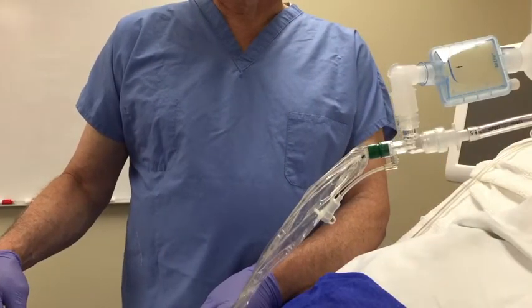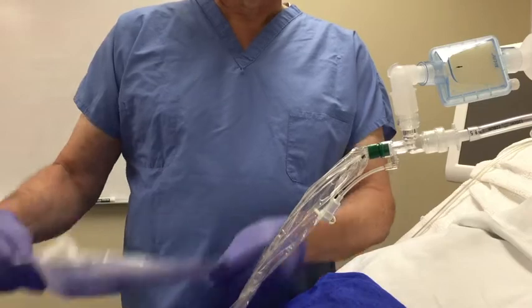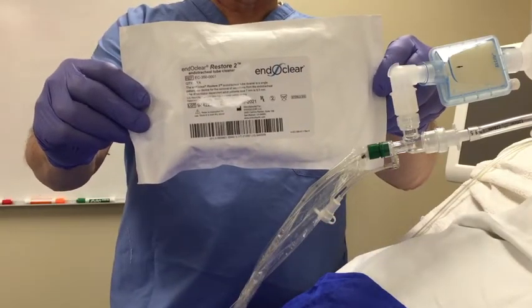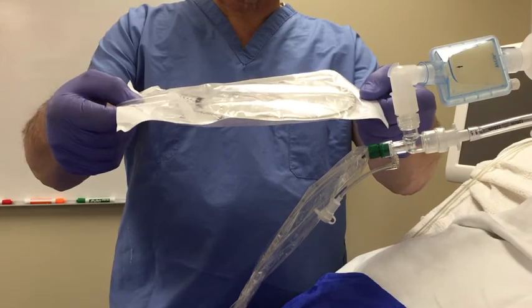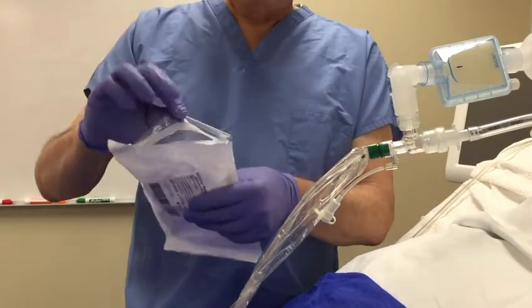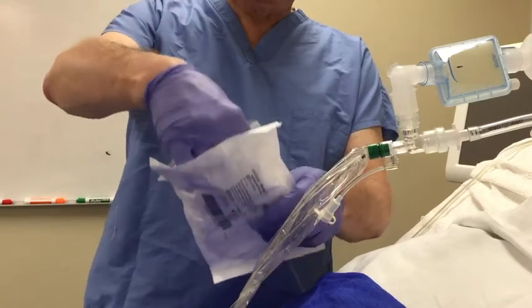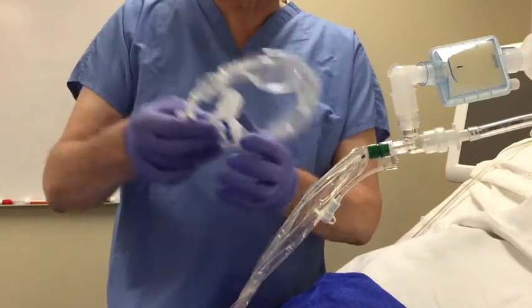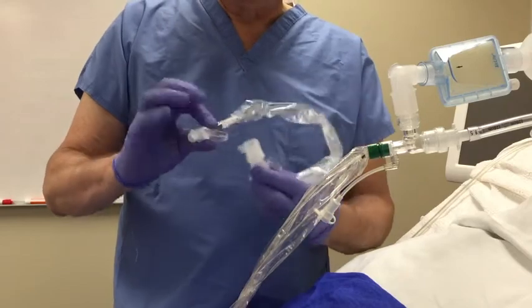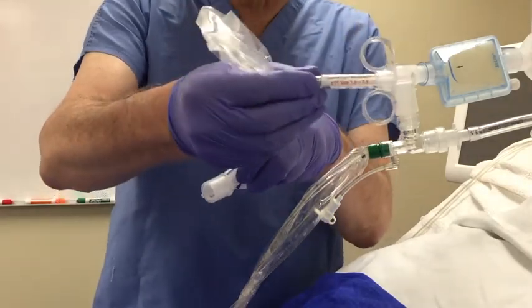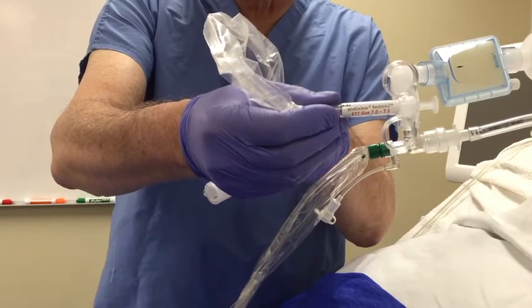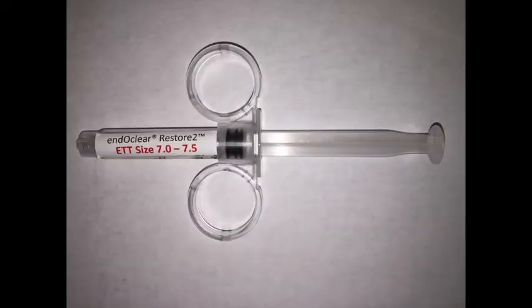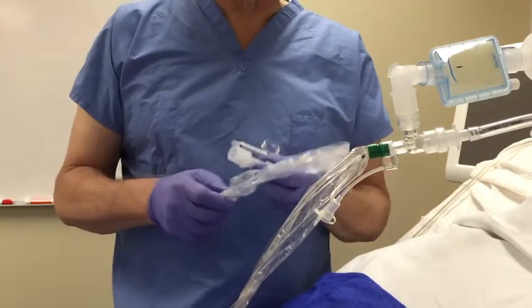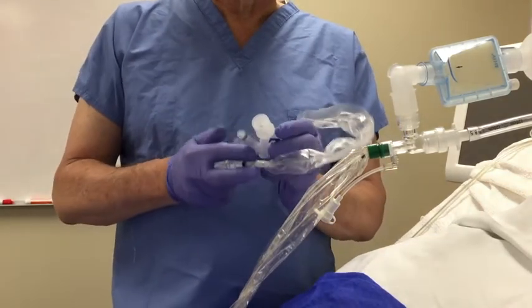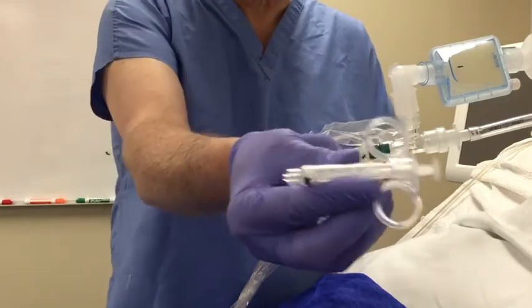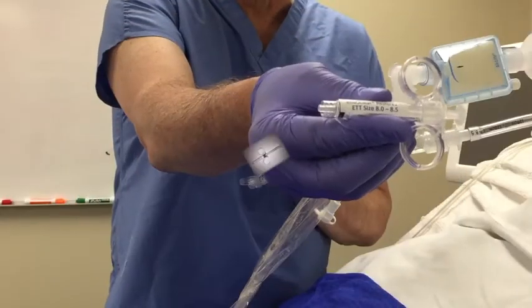As this is just a clean procedure, sterile gloves are not required. The Restore 2 package is clearly labeled and has a rather small footprint for easy storage. First, the package is opened and the device removed. It comes already attached to a syringe that is appropriately sized for 7 to 7.5 endotracheal tubes. If the endotracheal tube to be cleaned is an 8 to 8.5, then the syringe labeled 8 to 8.5 is substituted.